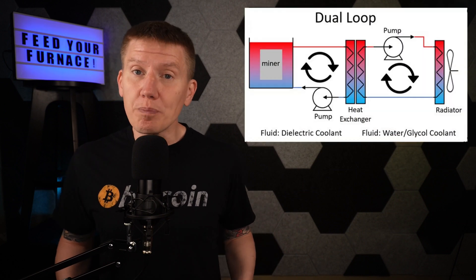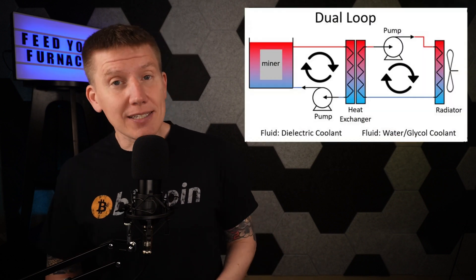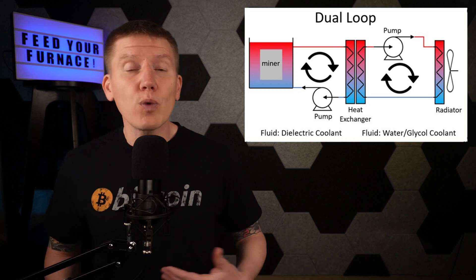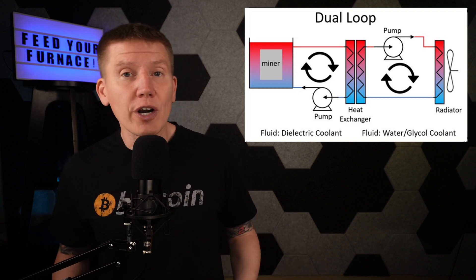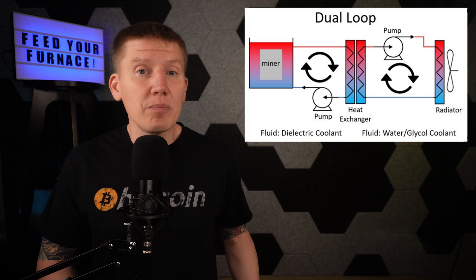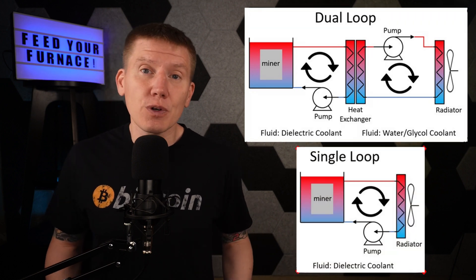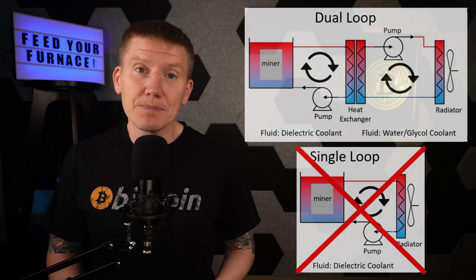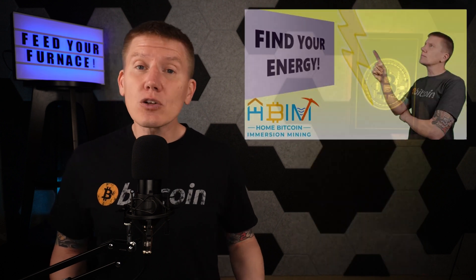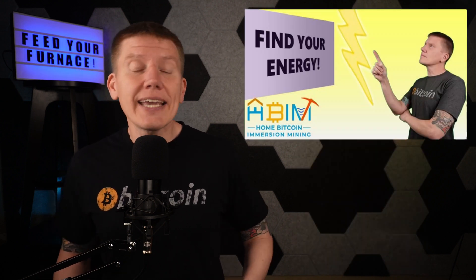I've put a few links below with more information. Before getting into the design, I want to note that all of this is only going to work well with a dual-loop Bitcoin mining system. Most all of the pumps, radiators, valves, and other hardware are made for glycol water mixtures, so a single-loop system circulating dielectric fluid will likely cause some problems. I covered single-loop versus dual-loop systems in a previous video if you want to know more.